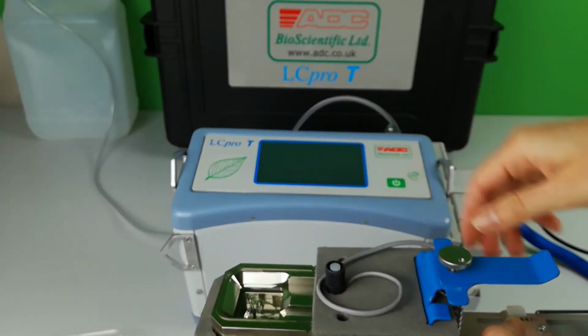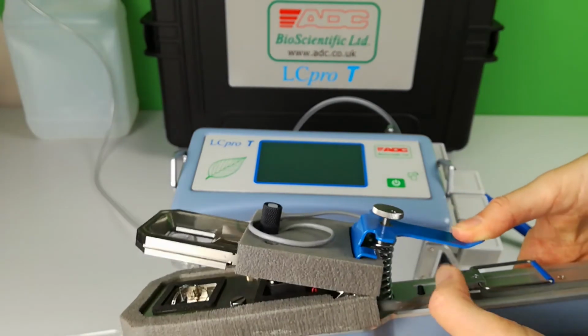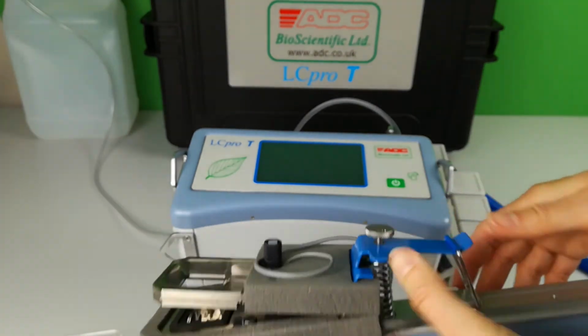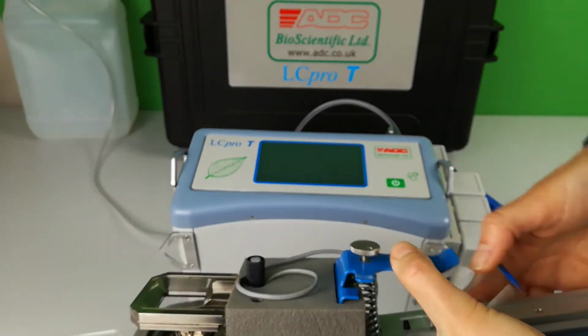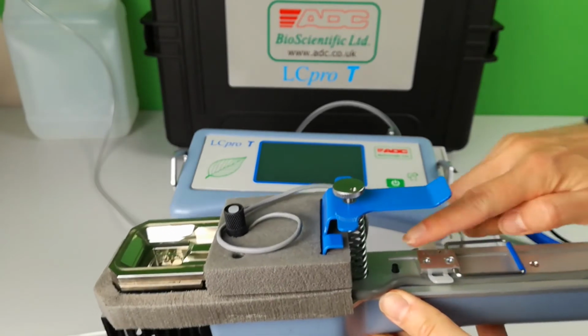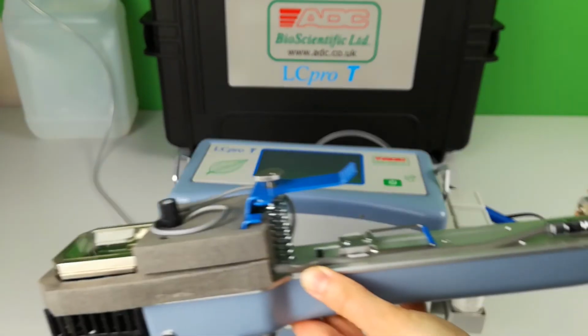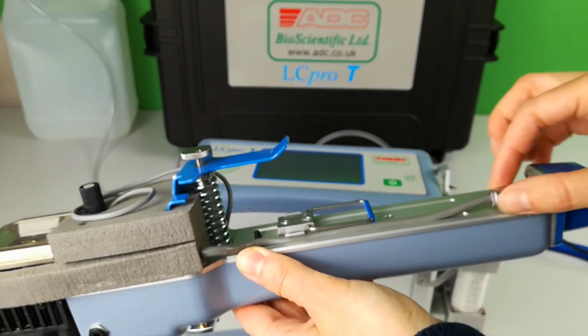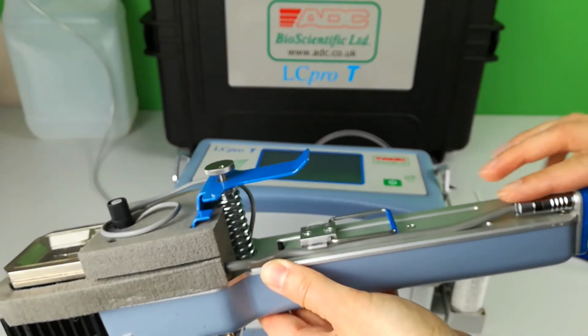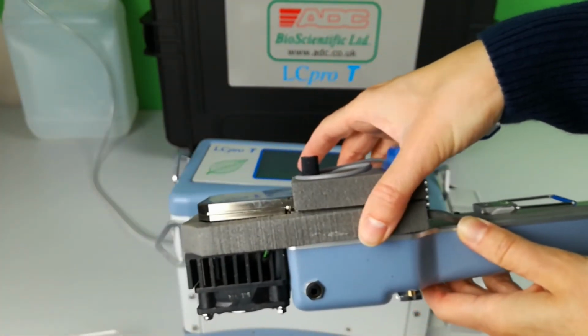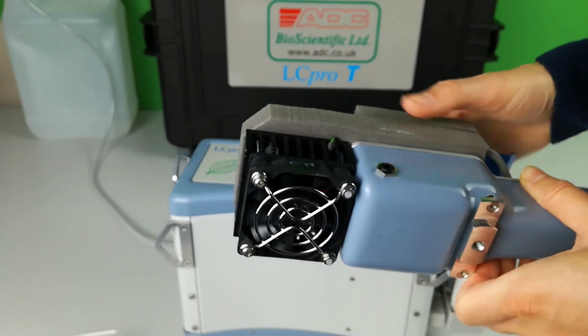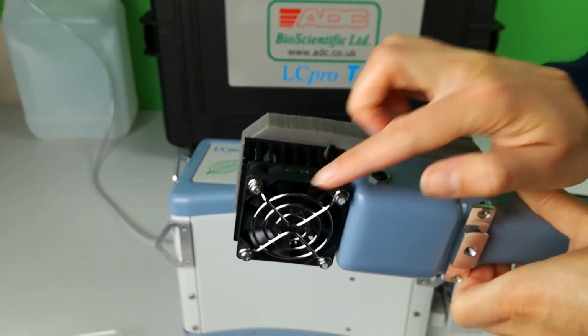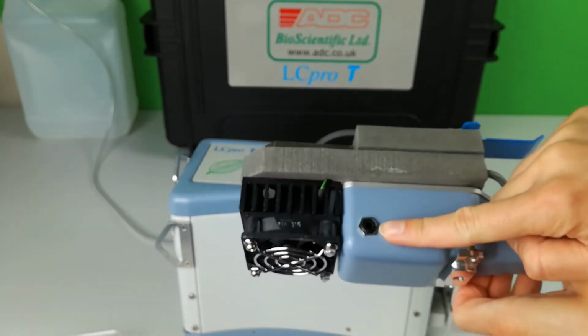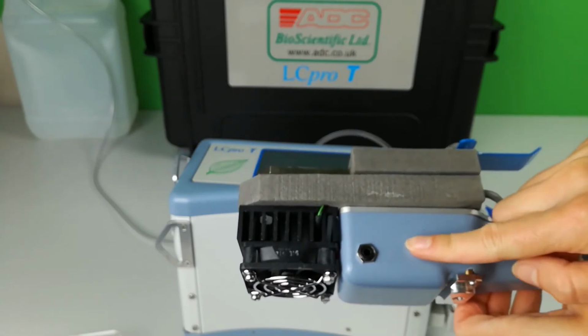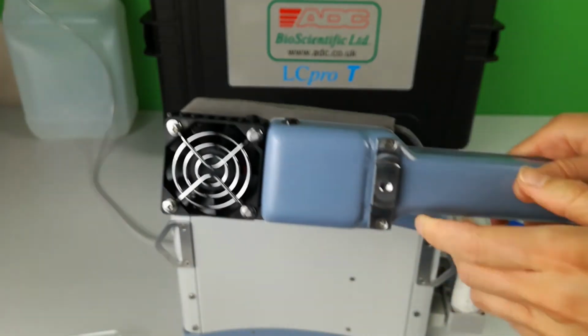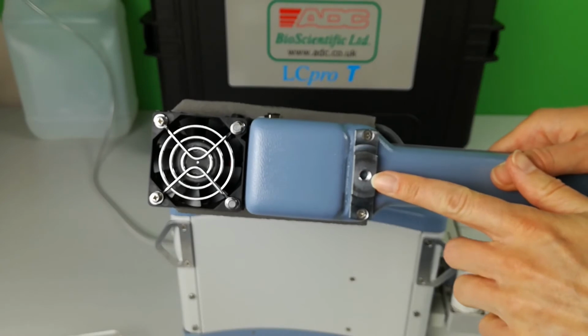The thumb latch allows you to store the chamber open to prevent gasket damage, and a small record button for instant data capture. A connector joins the chamber to the handle. Underneath the lower jaw is a heating element or heat exchanger, together with a pot adjuster for calibrating CO2. A tripod mount is included underneath.